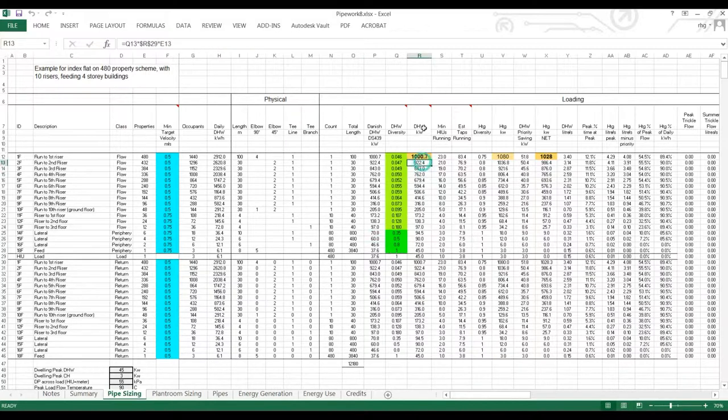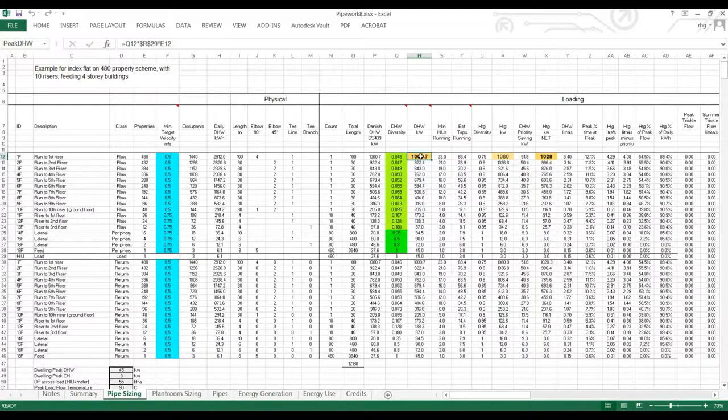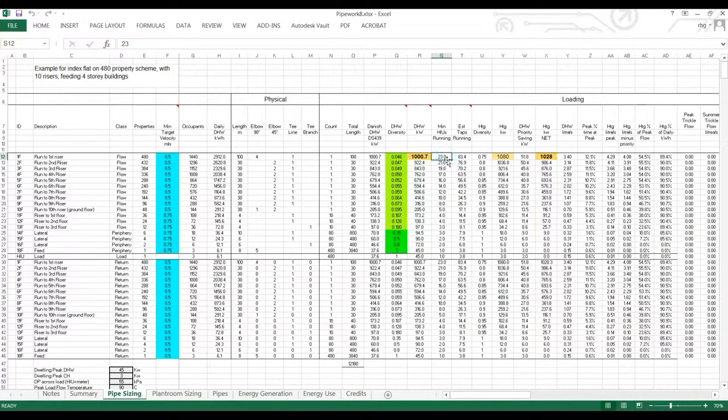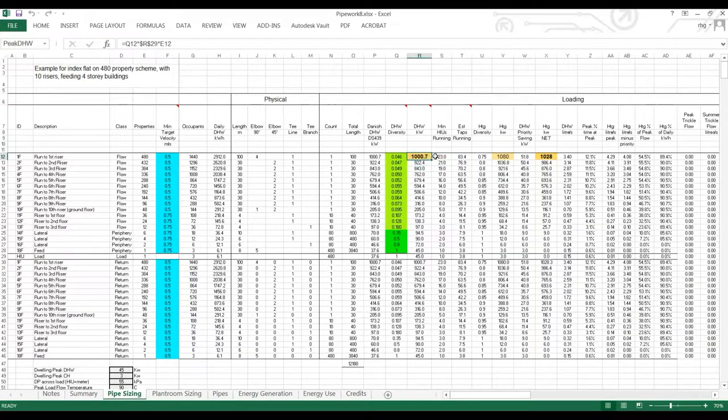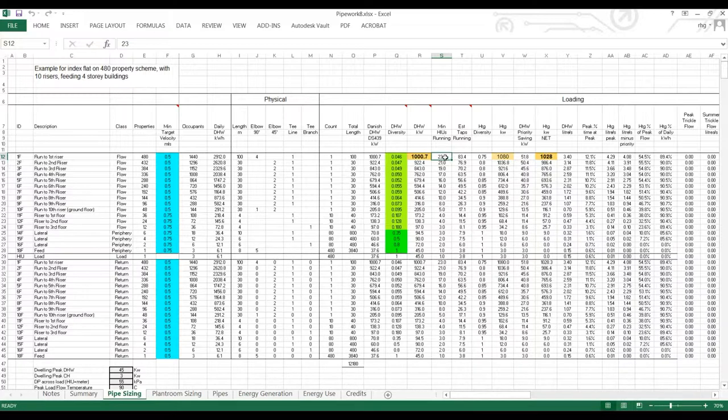This then moves on to the calculated domestic hot water load, diversified load. Now coming out of the plant room we have just over a megawatt's peak load on domestic hot water. From this we can determine the minimum number of HIUs running. So to deliver this load we know what an HIU is capable of putting out. We know the minimum number running. So this is used in hot water priority calculations.